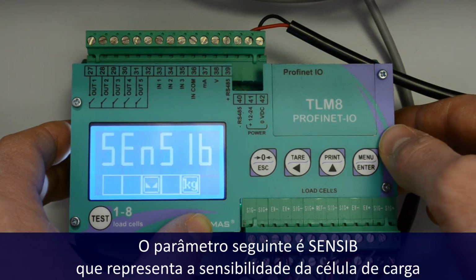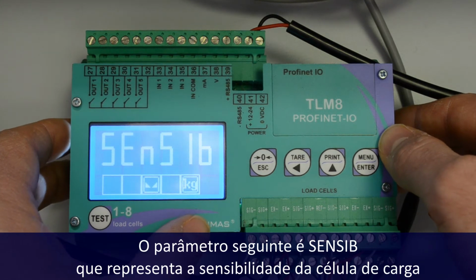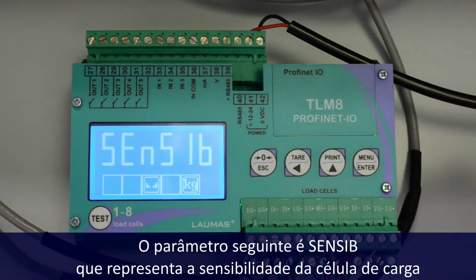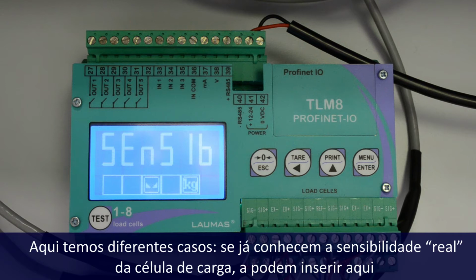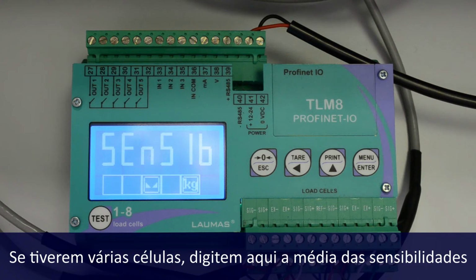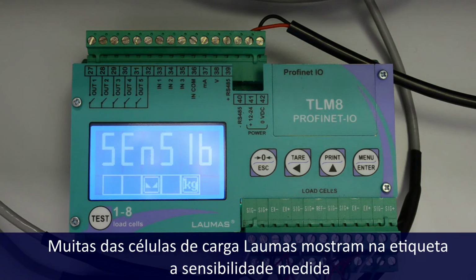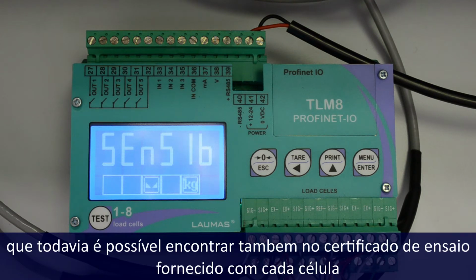The next parameter is sensib, which stands for the load cell's sensitivity. Here we have different cases. If you know the measured real load cell sensitivity, you can put it here. If you have more than one load cell, type here the average of the sensitivities. In many LAUMAS load cells, you have a label with the measured sensitivity, and you may also find it on the test certificate coming with every cell.